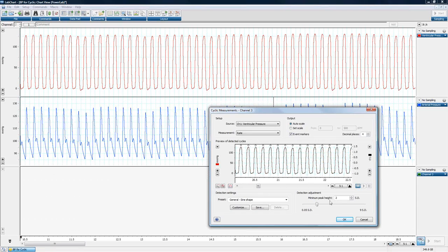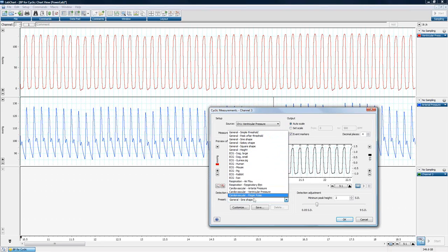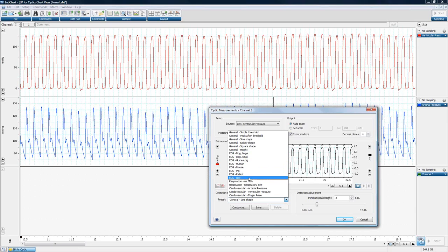Further down the page are pre-built detection settings. Since most customers make consistent measurements on specific signals, there are many presets: general ones like square shape, spiky shape, sine shape, and simple threshold; ECG presets for dog, guinea pig, human, mouse, pig, rat, rabbit; respiration signal presets; and presets for cardiovascular PowerLab and finger pulse transducers.